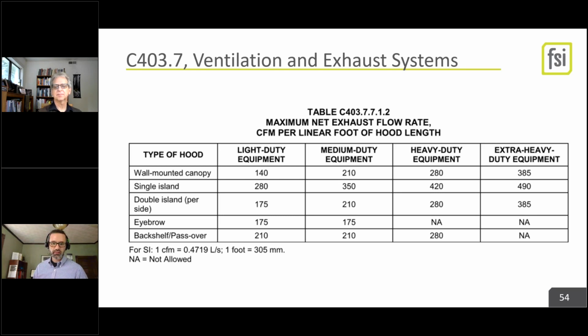So filters are intended to be cleaned. Let's start with that premise. In an adequately maintained building, what goes on is that the filter ramps the fan over time if you have airflow measurement, or you get less air out of the same fan over time as you get dirtier and dirtier filters. So depending on that answer, the fan might use slightly more power with a dirty filter, particularly where you're trying to provide the same continuous amount of airflow and you're measuring that. So you're ramping the fan as the filter gets dirtier. It's a modest effect. We've tried building that into an energy model, and it turns out that's somewhat difficult. You just got to take an escalation on the fan power.